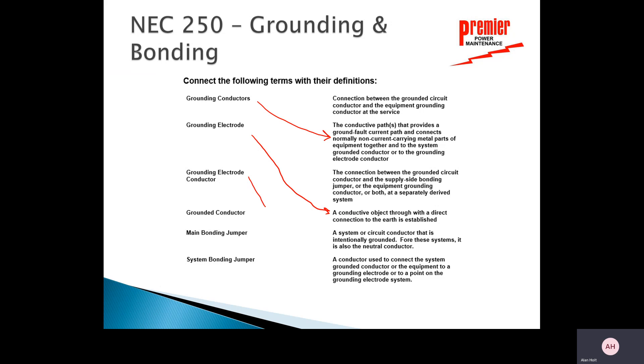The grounding electrode conductor is the conductor used to connect the system grounded conductor or the equipment to a grounding electrode or to a point on the grounding electrode system. That's our connection right down to the grounding electrode.